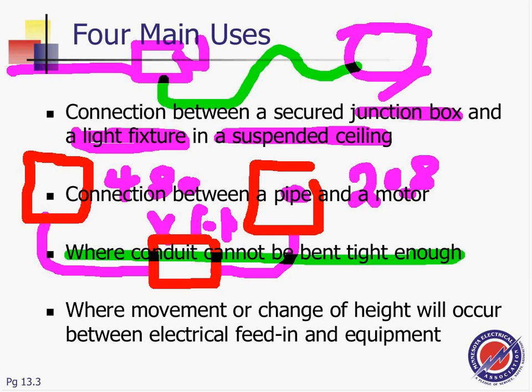Where movement or change of height will occur between the electrical feed and the equipment. The equipment movement, we talked about this, when things move, like in machines, or a change of height occurs between the electrical feed and the equipment. Back to tying to the equipment because of vibration or height or whatever. So that's another use for the flex.